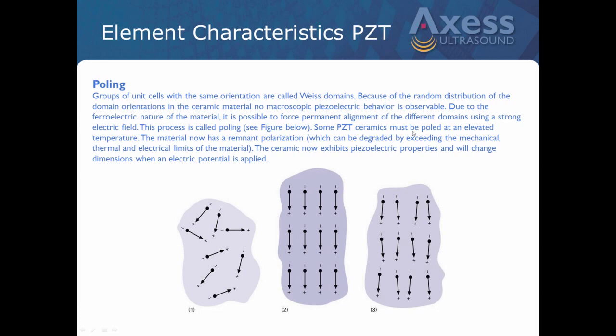So what the array manufacturers have to do, after they've made that array, the crystal itself, is orient it in the right position so that it can be used as needed and correctly. So this is figure 1 here. It kind of shows you a picture of the array element coming out, forming and so on. Essentially, in order to pole these properly, they have to apply a high voltage, high powered electrical current to the element, and then they also have to add heat to that.